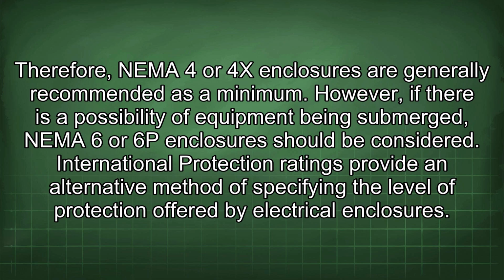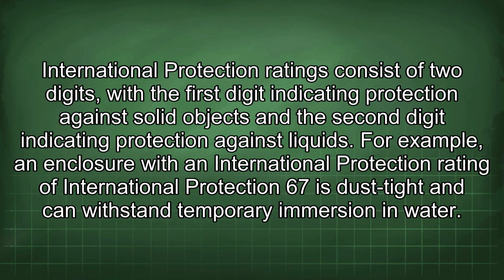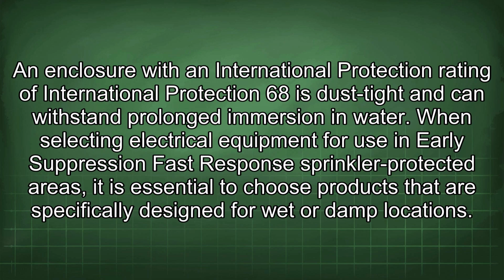International protection ratings provide an alternative method of specifying the level of protection offered by electrical enclosures. International protection ratings consist of 2 digits, with the first digit indicating protection against solid objects and the second digit indicating protection against liquids. For example, an enclosure with an international protection rating of International Protection 67 is dust tight and can withstand temporary immersion in water. An enclosure with an international protection rating of International Protection 68 is dust tight and can withstand prolonged immersion in water.